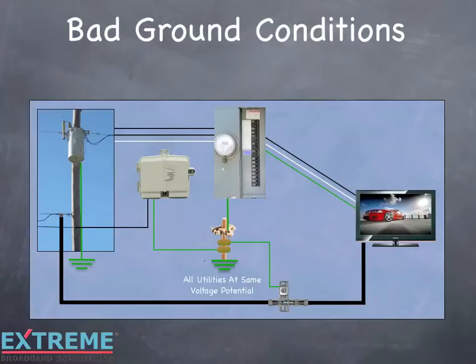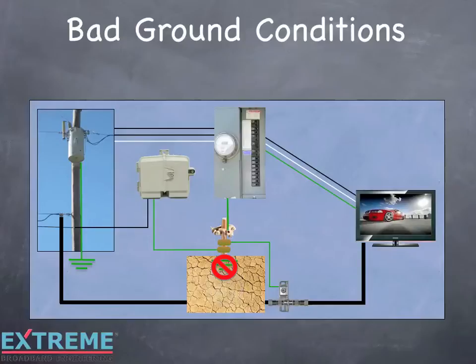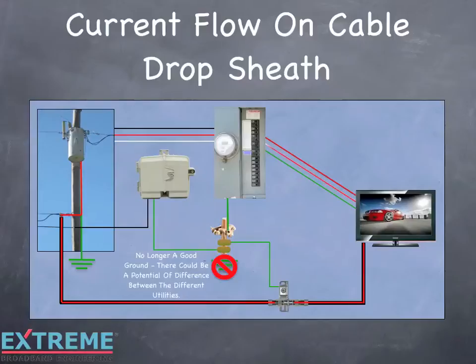There may be times when the common ground that the power utility establishes is no longer a good ground point. This can happen due to poor soil conditions such as rocky, sandy, or very dry soil where the ground rod does not make good contact with the soil. No longer a good ground, there could be a difference of potential between the different utilities. When this happens, each utility could be at a different ground potential. This can cause a voltage drop across the coaxial cable shield, which results in current flow on the shield of the coaxial cable. Now some of the return AC current flows on the coaxial shield back to the transformer, along with the normal neutral path.